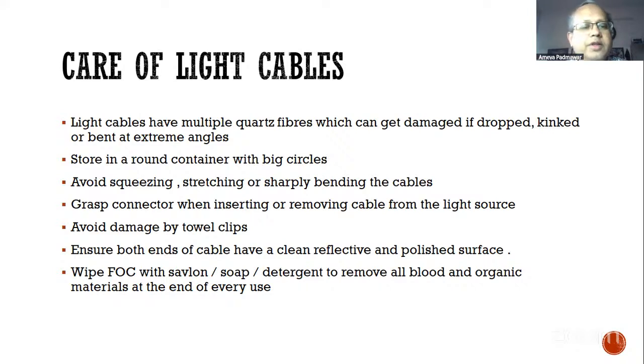So you should always store it by making big circles of the cable, especially when you're storing it. It has to be in a wide round container. Avoid making hairpin bends on it. Whenever you're rotating the cable, especially when you're using the 30-degree or the 45-degree oblique scopes, you have to hold the steel part of the cable, the connector, and rotate it, and not the gray or the green part of the cable and twist it, because otherwise it will get fractured.